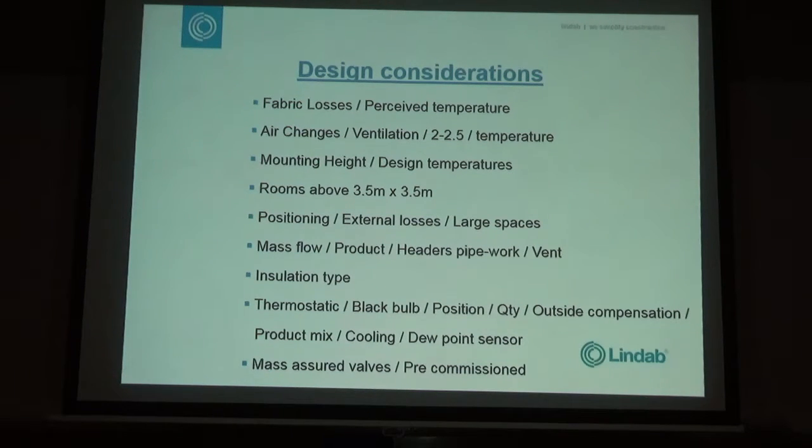Now, radiant heating doesn't heat the air, as I mentioned before. So if you've got a naturally ventilated building, or you've got a building where you've got a lot of air change, a laboratory, something like that, radiant heating isn't going to be your thing because it's not going to heat your air changes above 2.5-3 air changes an hour. So if you've got a lot of air changes, then radiant heating's not going to work because it's not going to heat it. Or you have to temper your heat change.